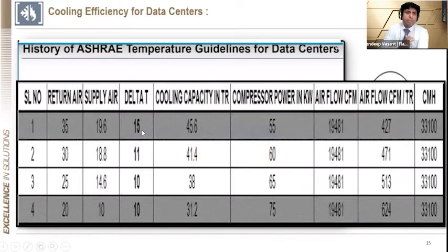So what impact happens on the cooling unit if we use the ASHRAE 18 to 27 supply air temperature? I have taken a case study of a 30 TR. Normally, most of the time in a small server room, they say let's operate at a low temperature. I should feel cold, thereby I assume that the rack would also feel cold. But there is a clearly defined ASHRAE document which says 18 to 27 is the supply air temperature.